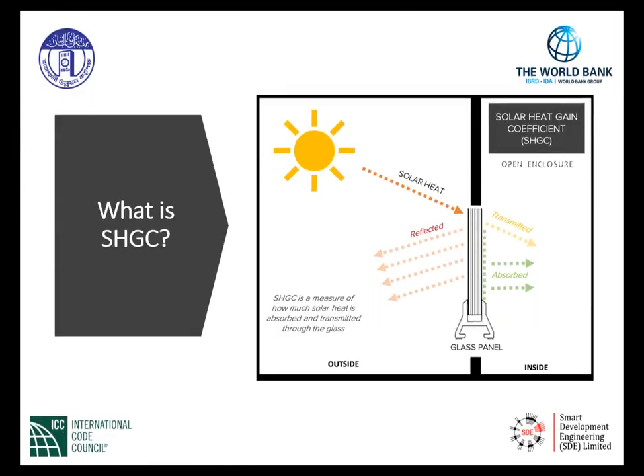All right, what is solar heat gain? It seems like a big word. Solar heat gain coefficient, it seems so technical. And if you want the technical, yes, there is one. The solar heat gain is the fraction of incident solar radiation admitted through a window, both directly transmitted and absorbed and subsequently released inward. It's expressed as a number between 0 and 1. The lower the window's solar heat gain coefficient, the less solar heat it transmits.